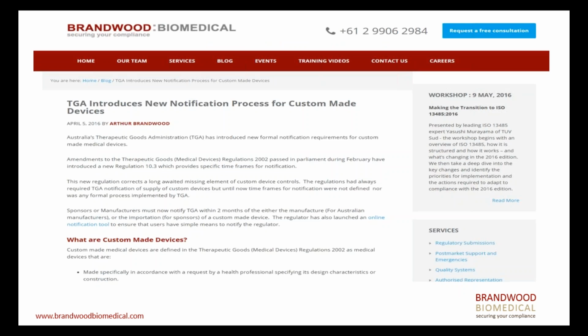Again, we do have that block I was referring to, so the TGA is now taking that step of putting tighter controls on custom-made devices. We see this as a positive move, and at the moment it's just a notification tool that's been established. In the regulations, it's always been that you have to notify the TGA of custom devices, but there were no time frames established, and there's no formal process implemented. This new online notification tool requires sponsors or manufacturers to notify the TGA within 2 months of importation of the custom-made device, and it is the first step to making sure there are appropriate controls on these types of devices. Please refer to our blog for further info, but the link is there as well.